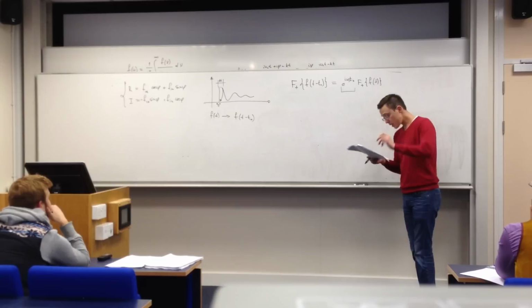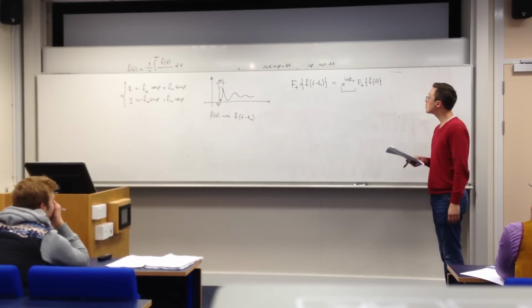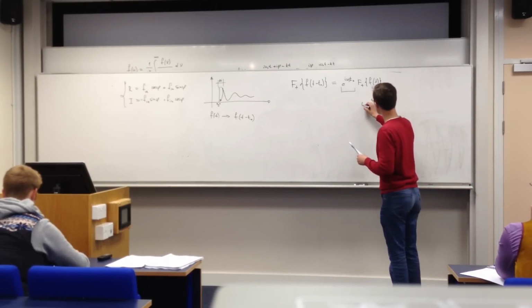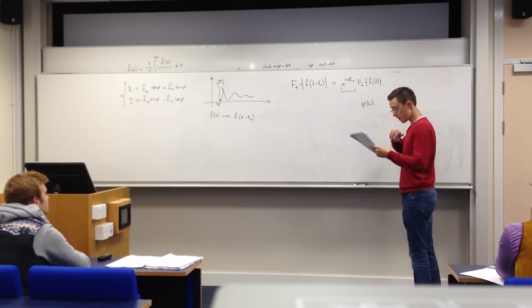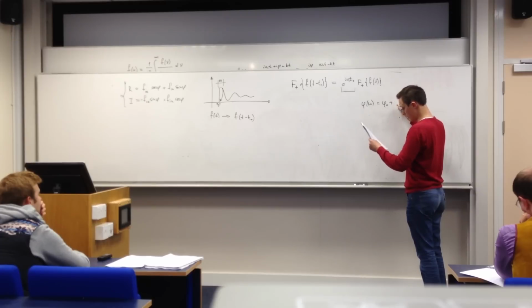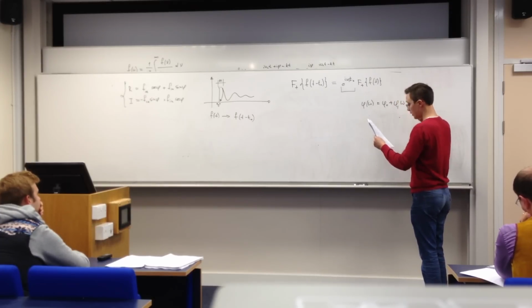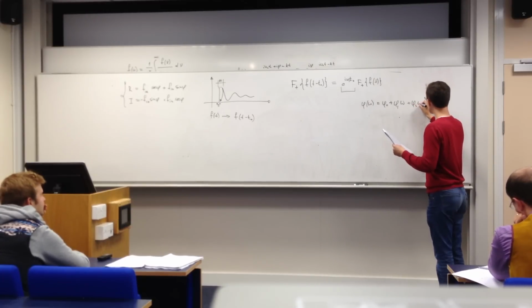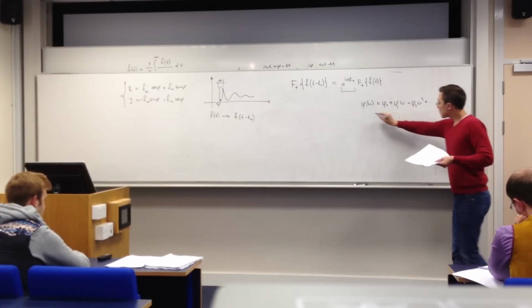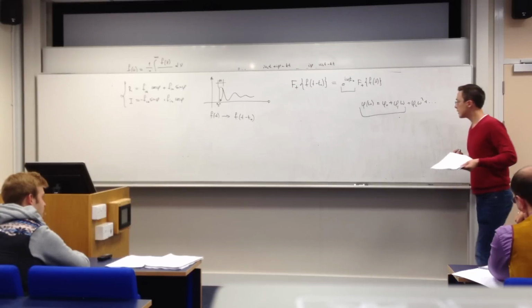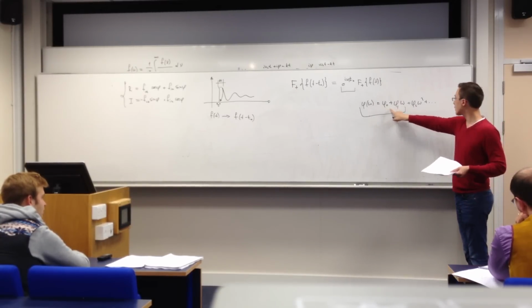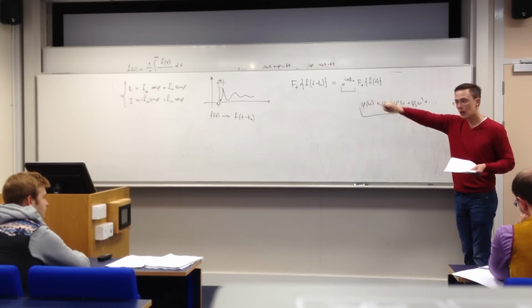However, many spectrometers also allow you to tweak quadratic and higher terms in the phase. So the phase, as a function of the frequency, would be our static phase phi 0, plus the term that is linear in frequency, phi 1 omega, plus phi 2 omega squared, and so on, a Taylor expansion. This, we have sensible physical grounds to expect. Yeah, this is always there, and this is the consequence of the dead time.